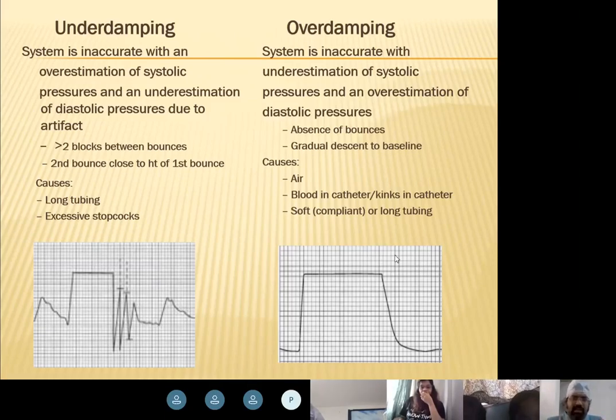It will tear from the inside, and after it tears from inside it will not work. You understand what I'm saying? That is the reason you use the fast flush, the flush coming from that blue line from the transducer. Don't use the flush from the syringe. With the syringe, there is a high chance that you will push it fast. The pressure will fray the line and the arterial line will no longer work. So you must understand what overdamping is.